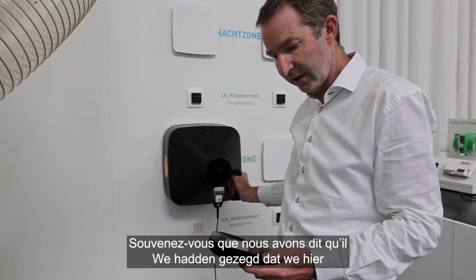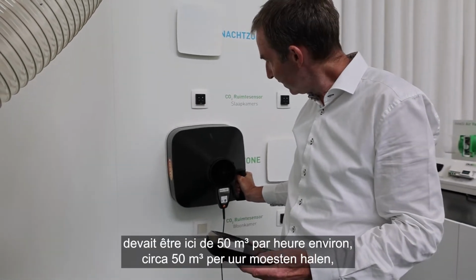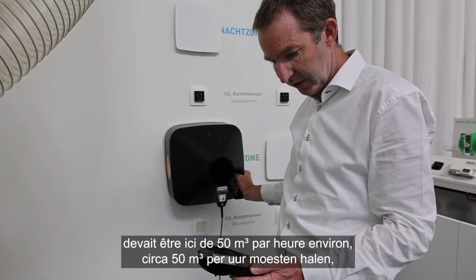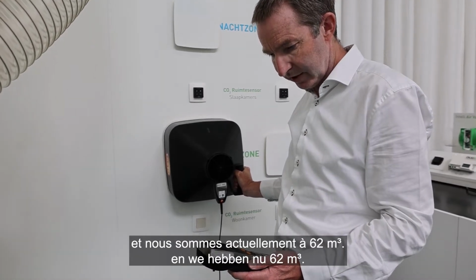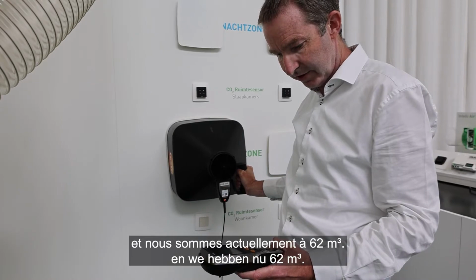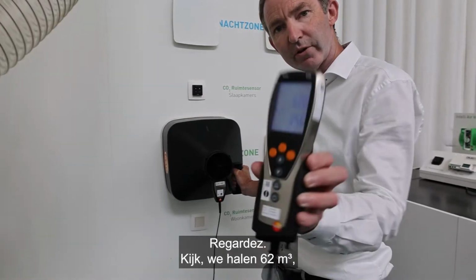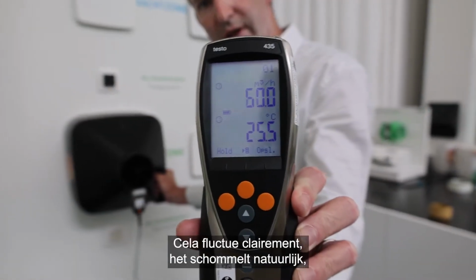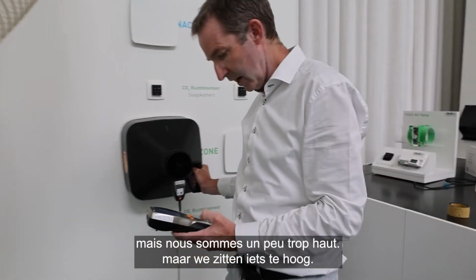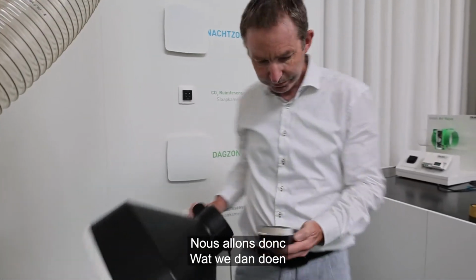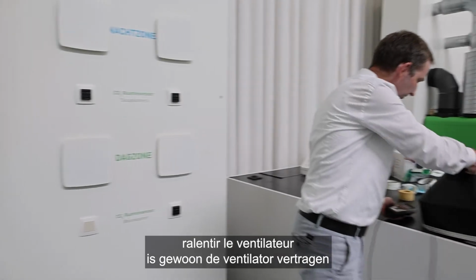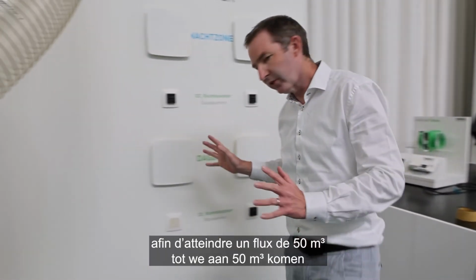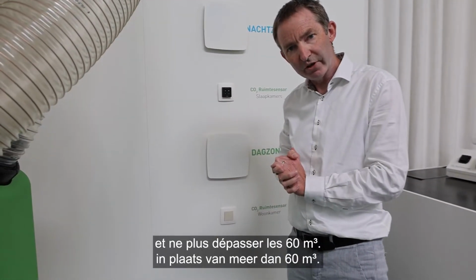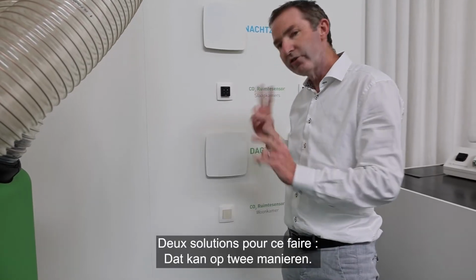Remember that we said that here we needed approximately 50 cubes an hour, and we are actually at 62. Look, we're at 62. It's obviously fluctuating, but we are a little bit too high. So what we will do is basically slow down the fan so that we reach 50 cubes as opposed to over 60. There's two ways we can do that.